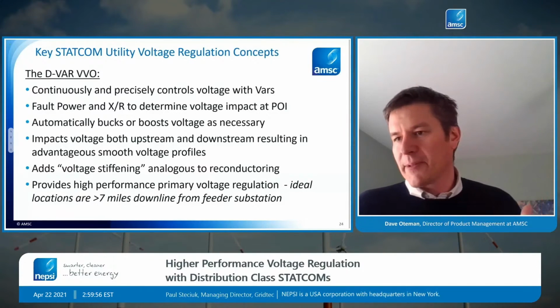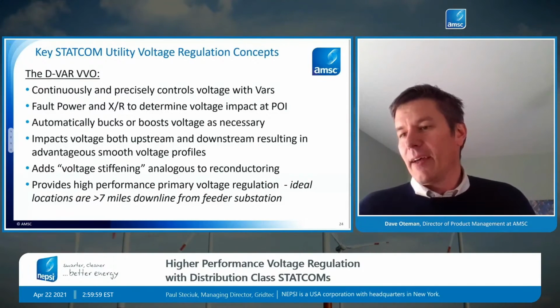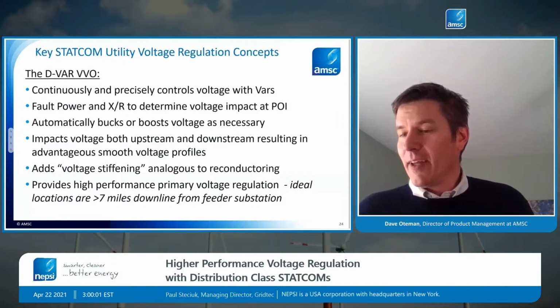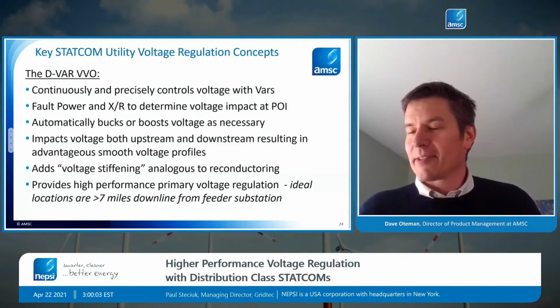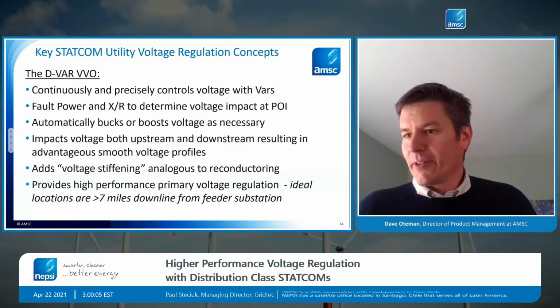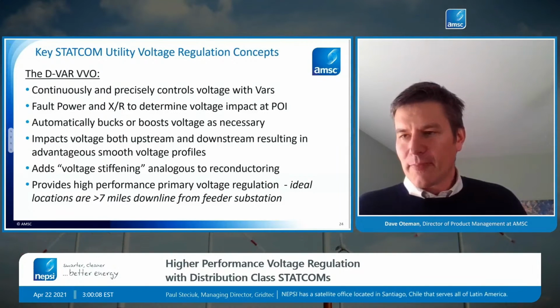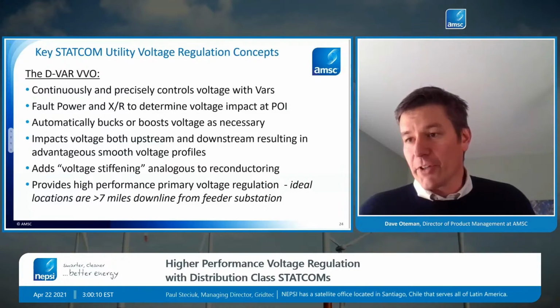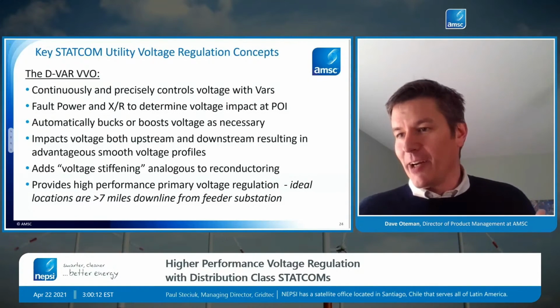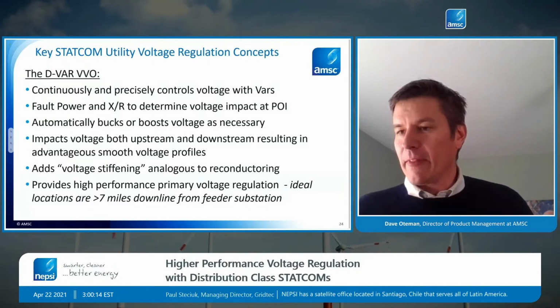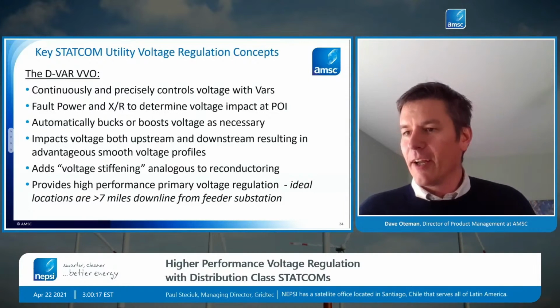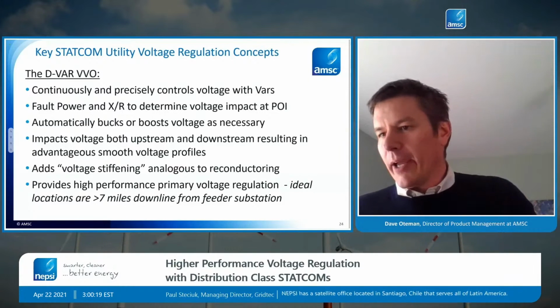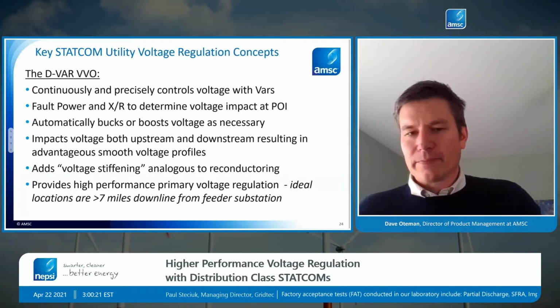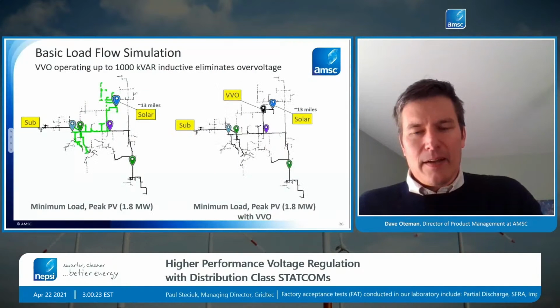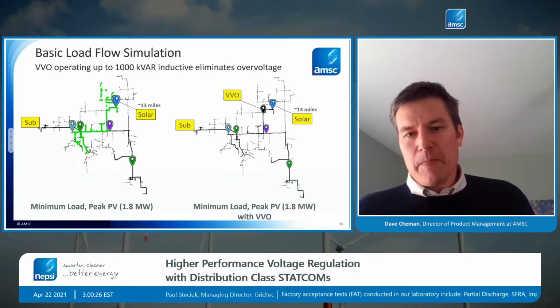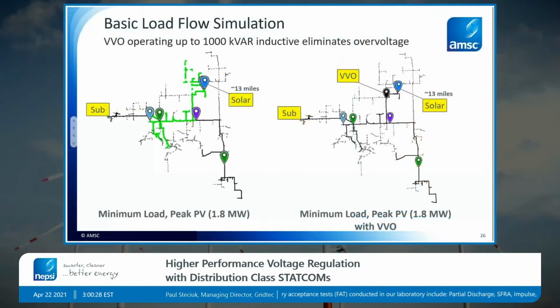So that recaps the key concepts of how a shunt STATCOM D-VAR VVO device is regulating voltage on a distribution feeder. And with that, I'll share a case study here where we're actually using the D-VAR VVO device on a longer feeder to enable a solar plant to be connected. Here's a study showing this connection in the CYME software.